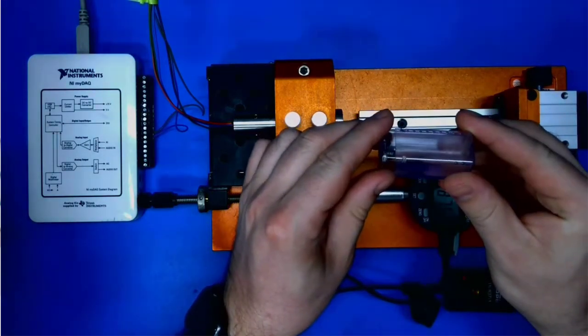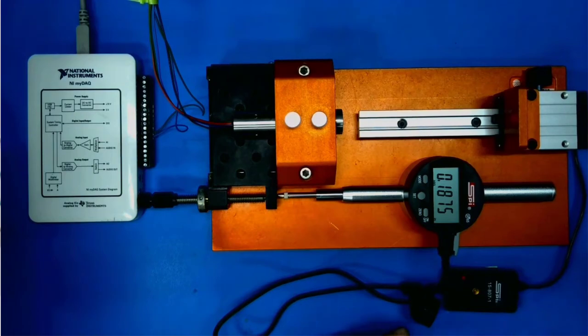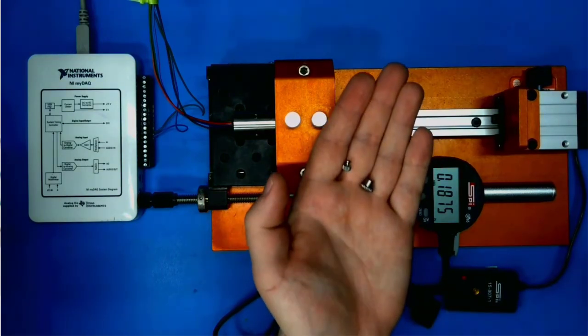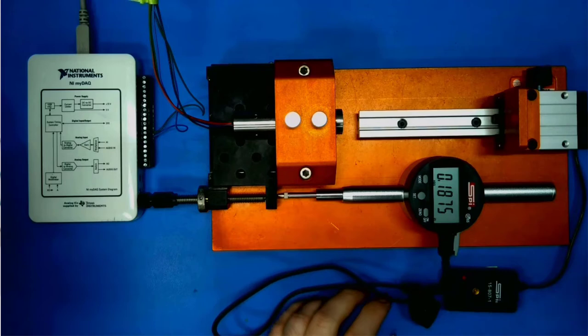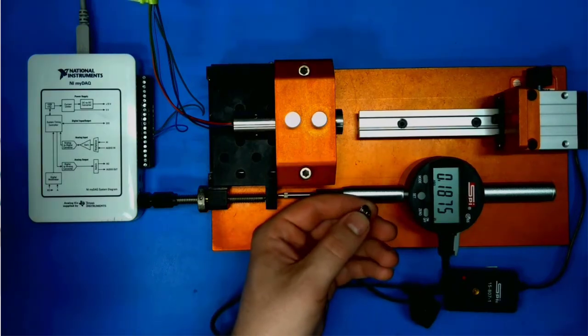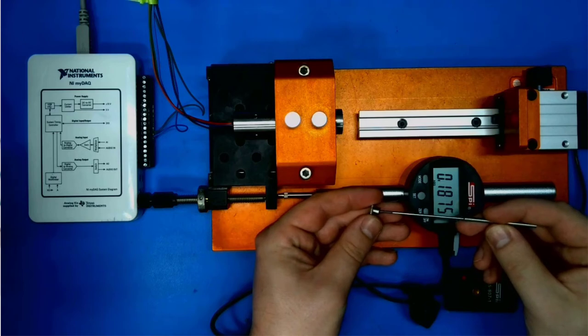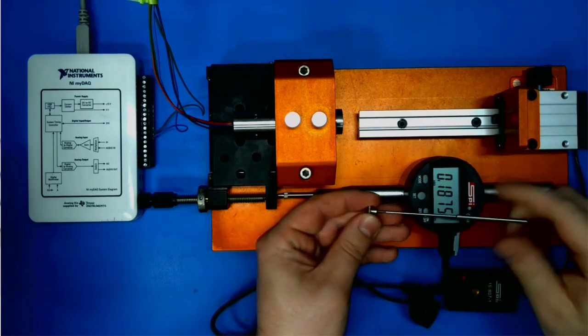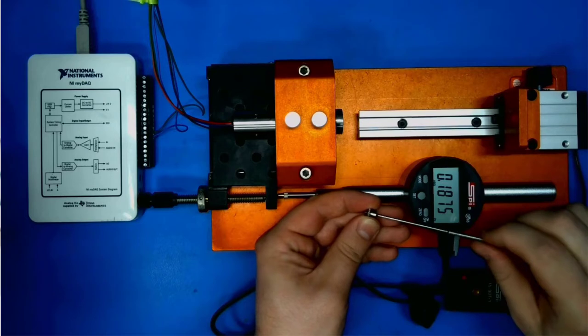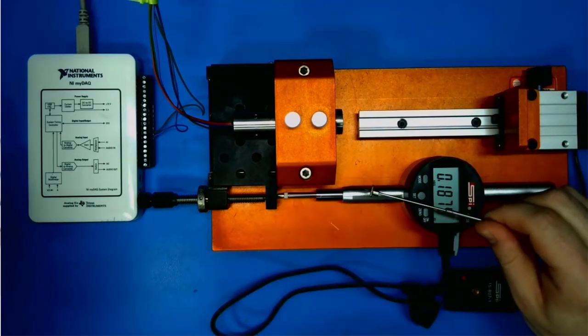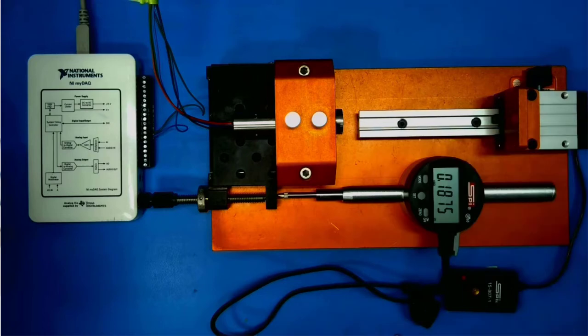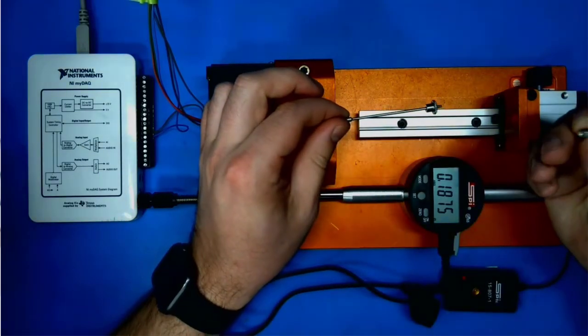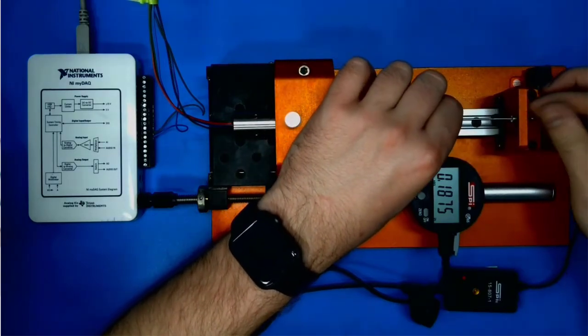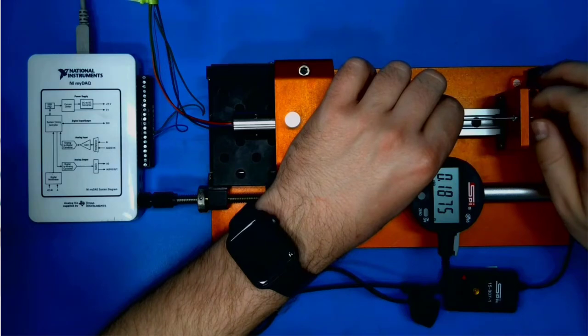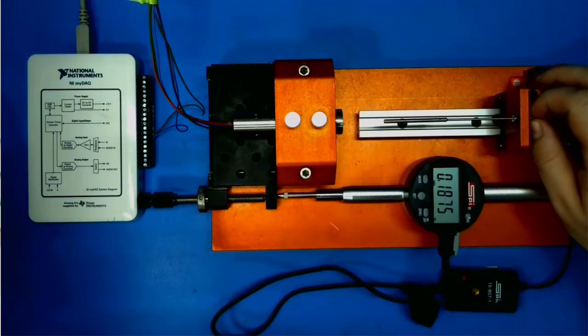Next, you're going to get the core nuts, of which there are 2. And the larger core nut with the flange goes on the transducer core with the flange facing backwards. Like that. Then it's going to go through this plate with the other core nut going on with the flange facing forwards. And you want to just barely snug this. You want the core to still be able to move.